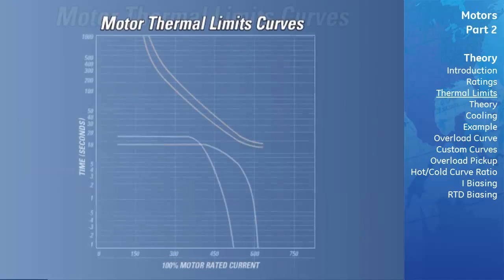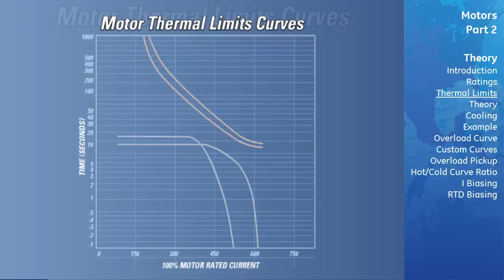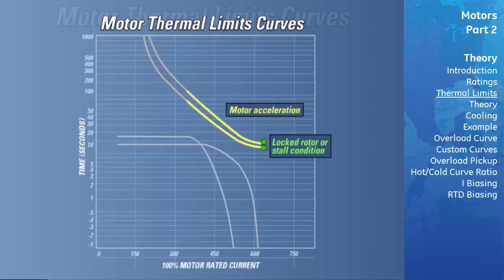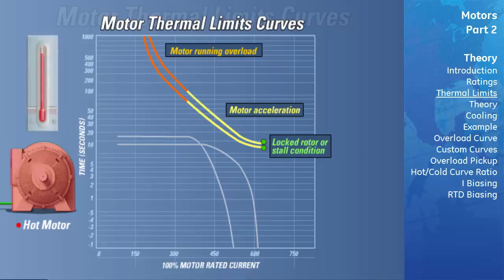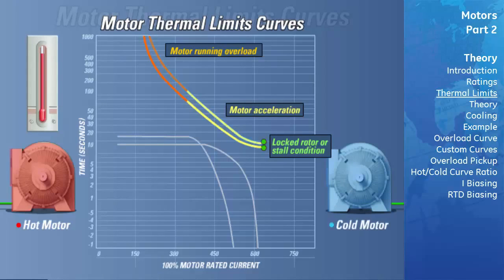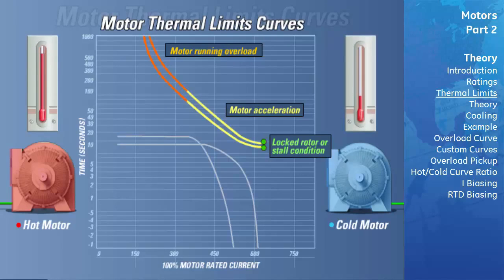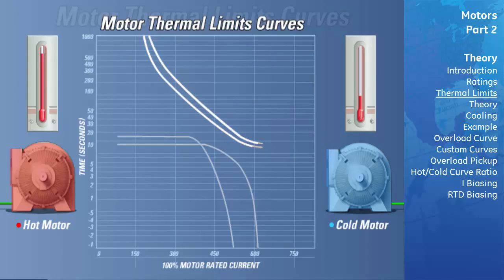Motor Thermal Limits Curves. The motor thermal limits curves consist of three distinct segments based on three running conditions of the motor: the locked rotor or stall condition, motor acceleration, and motor running overload. Ideally, curves have been provided for both a hot and cold motor. A hot motor has been running at full load such that stator and rotor temperatures have settled at their rated temperatures. A cold motor has been stopped long enough that rotor and stator temperatures have settled at ambient temperature. For most motors, the motor thermal limits are formed into one smooth, homogeneous curve.